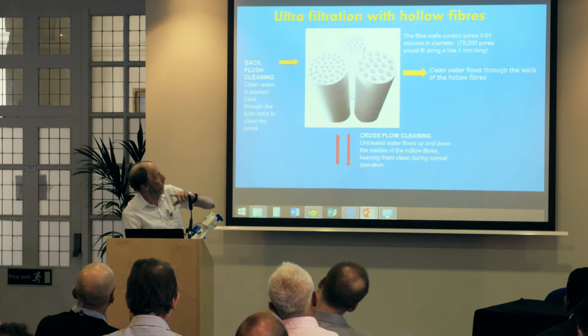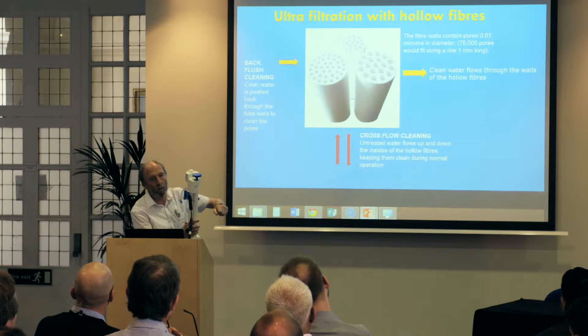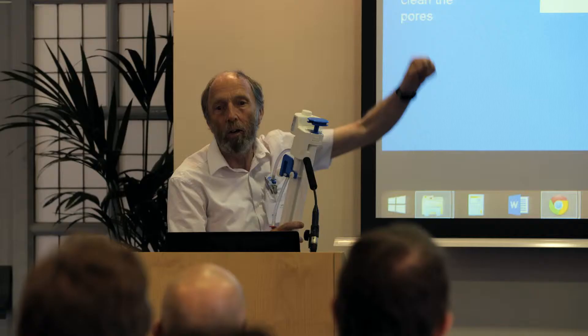It's cross-flow. We have a pump — you need pressure for ultra-filtration. The water goes up the tubes, then there's an air pocket. When you release the pump, it goes down again, so we have continuous cross-flow and the surfaces are kept clean.